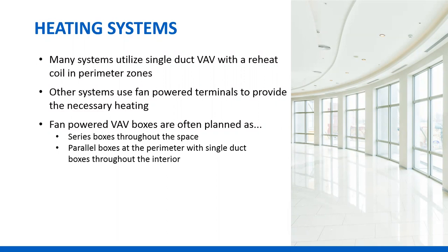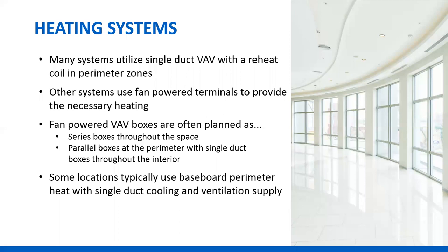We're seeing more people using series boxes and fewer using parallel boxes. In cold climates, baseboard perimeter heat is still being used with single duct cooling and ventilation. Wisconsin is an example primarily using baseboard perimeter heat. Although in places like Montana, we're seeing the single duct VAV box. Climate doesn't necessarily tell the whole story.